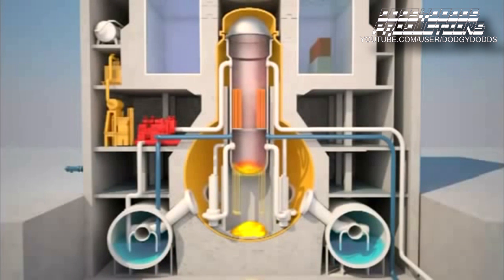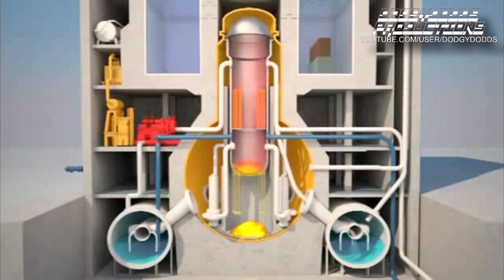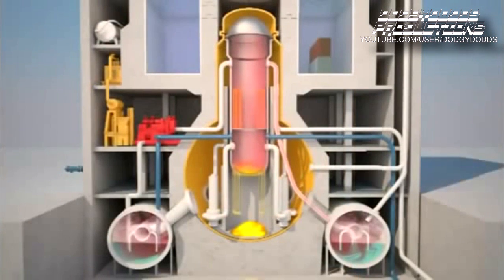Normally, when mixed with air, hydrogen catches fire and explodes. However, the containment building was filled with nitrogen, an inert gas that avoids the presence of oxygen, so at this stage there was no risk. As the steam pressure rose to a dangerous level in the reactor vessel, the depressurizing valves opened. Gas was forced into the wet well suppression pool by a venting line. The water acted as an efficient filter by trapping much of the radioactive elements. But the water was no longer cooled because the emergency diesel generators were out of order, and it soon began to boil, thereby reducing its filtration capacity.